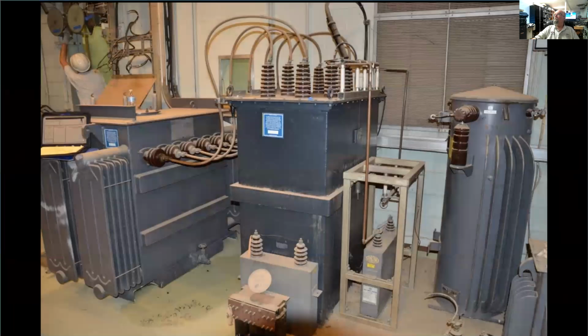On the PA side, this is the high voltage transformer, a three-phase transformer supplying PA voltage to a three-phase rectifier immersed in oil, 148 gallons of oil to be exact. Off to the left is a general purpose utility transformer that takes the 4160 volts AC three-phase input and gives us 220 or probably 208 three-phase and 115 utility for other systems here. This is big stuff; that one plate transformer weighs 5,000 pounds.